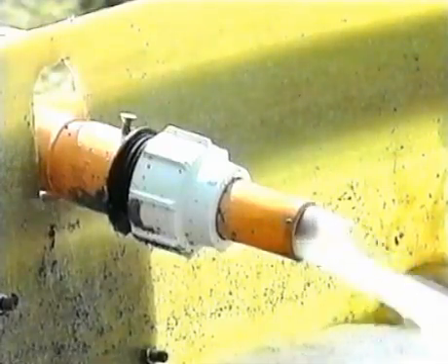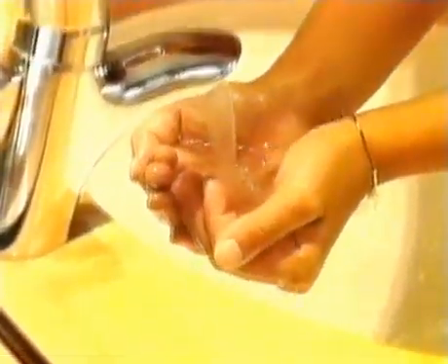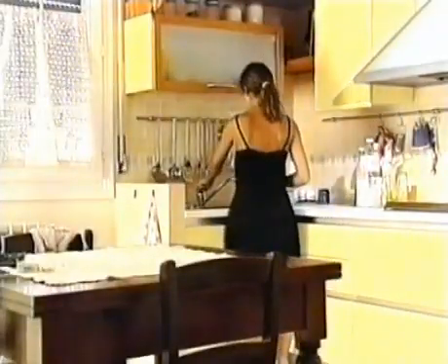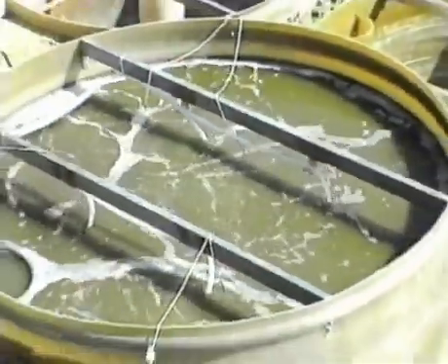The size of the chambers is based on the concept of the standard inhabitant, which defines the specific load of the inhabitant in both hydraulic and organic terms. To be on the safe side, the size of the disposal system is based on the maximum values encountered. The water supply needed for washing and waste disposal is approximately 200 liters per person per day, and the organic load is about 75 grams of biochemical oxygen demand per person per day.